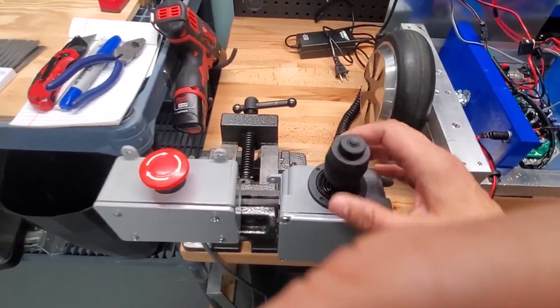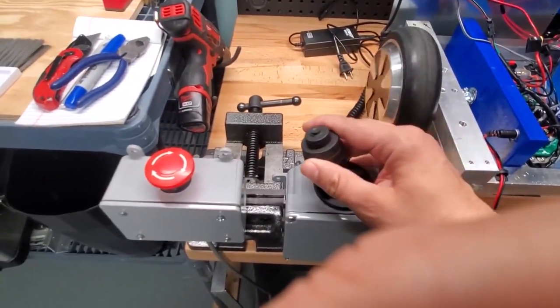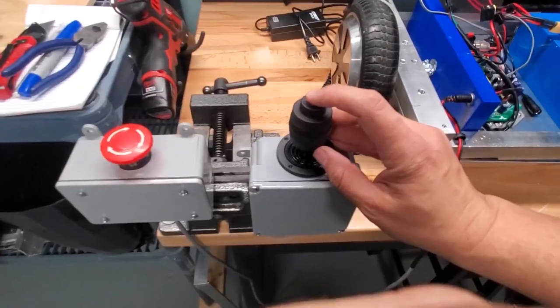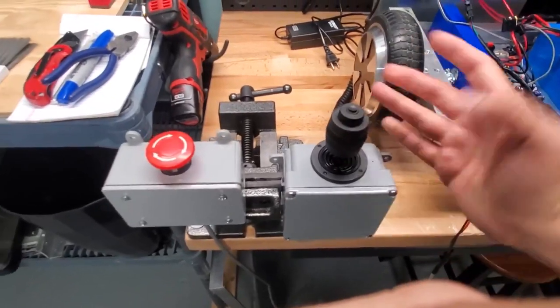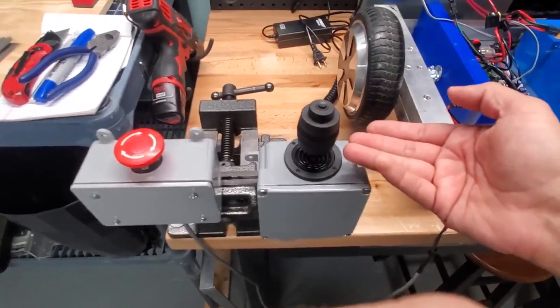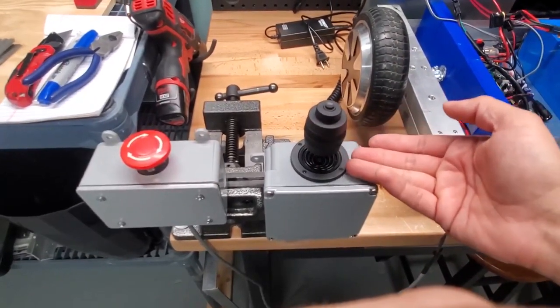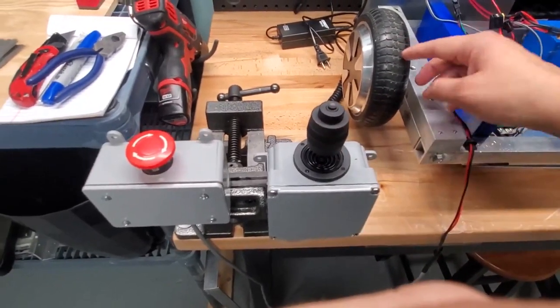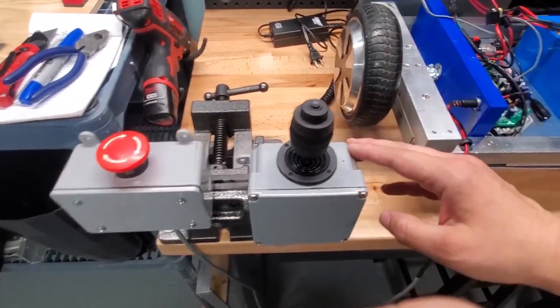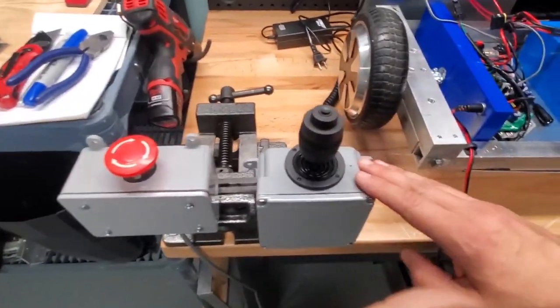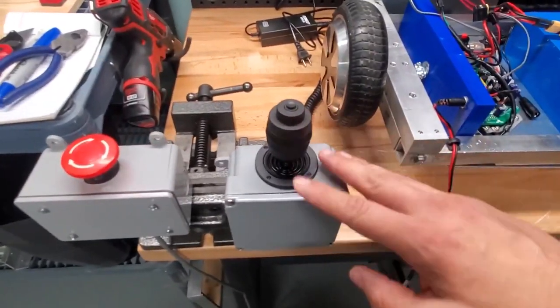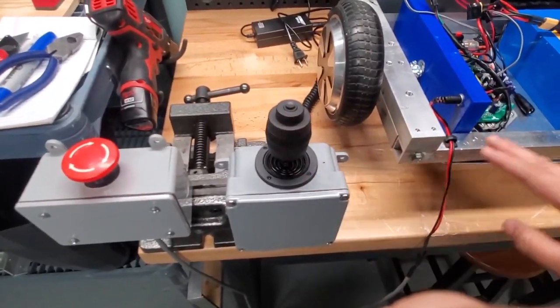So you go forward, back, left, right. If you ever turned it on, and you're not touching the joystick, and the wheels are trying to move a little bit, that they're creeping or whatever, then this may need to be calibrated.